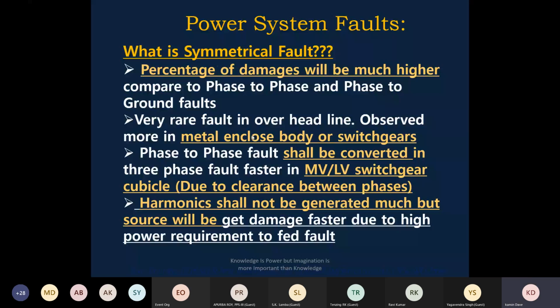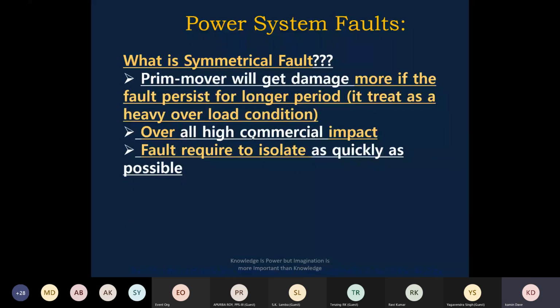Prime mover will get damaged more if the fault persists for a longer period in case of the three phase fault. Overall it is a high impact, commercial impact, because it affects the prime mover plus generator, both equipment. Fault is required to be isolated as quickly as possible. If it is a 400 kV network, this fault should be cleared within 100 milliseconds. If it is a 220 kV network, it should be cleared in 165 to 170 milliseconds. Normally.